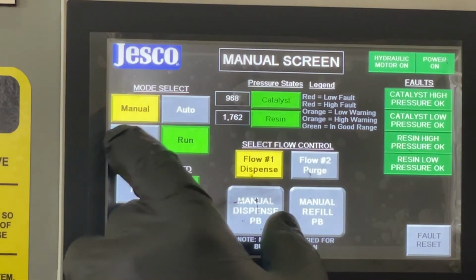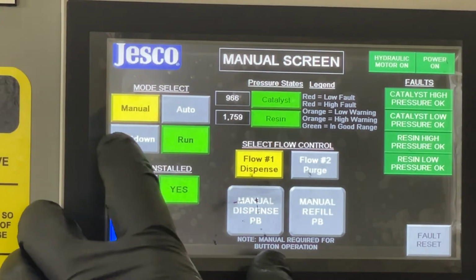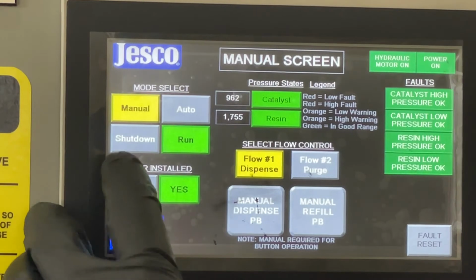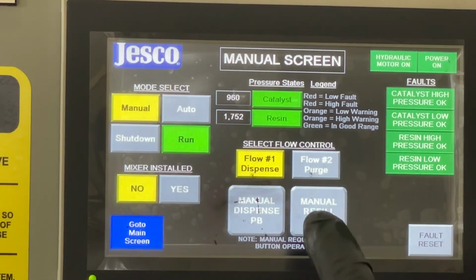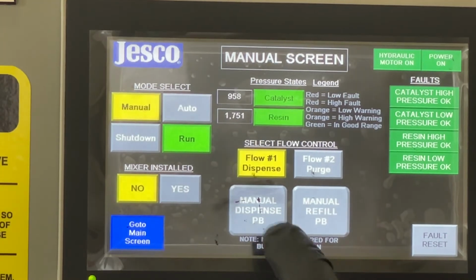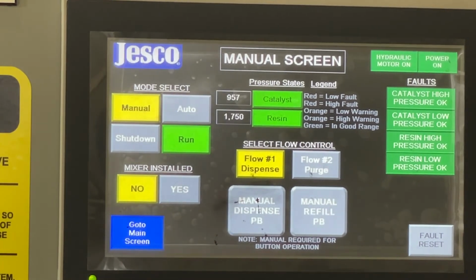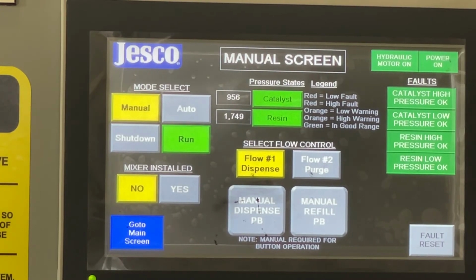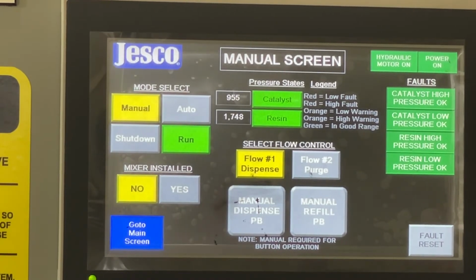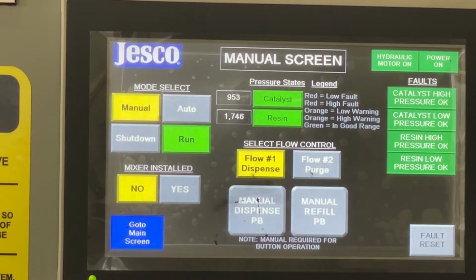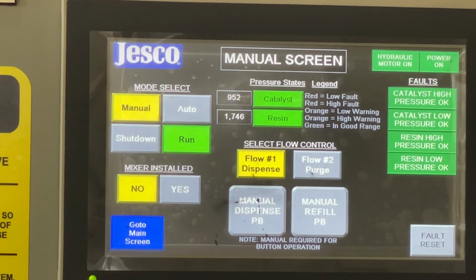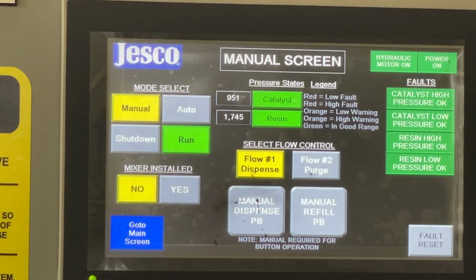We have a shutdown button, which when you are done for the day or before a weekend shutdown, you would select the shutdown, remove the mixer from the front end of the applicator. You would have mixer installed no. You would hit manual dispense once, and the metering unit would drive itself all the way down, hit the low or the meter empty limit switch at the bottom of the unit. And as soon as that is engaged, the system will stop, and you are able to shut the machine down for that length of time.